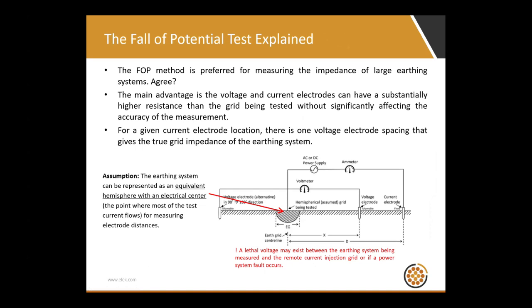Let's talk about the actual test. The fall of potential test is a very common and popular test. It has a significant theoretical and practical advantage, and that's that the voltage and current electrodes can have a significantly higher resistance than the grid being tested. Therefore, we're not concerned about the impedance of the leads when we are performing the test, apart from ensuring that we can supply sufficient injected current.